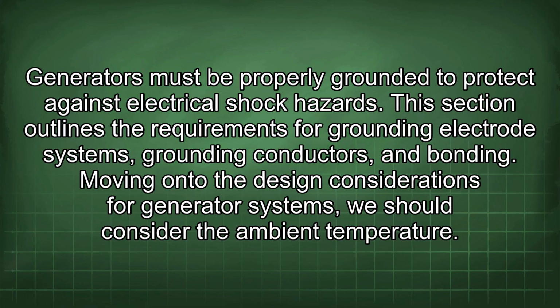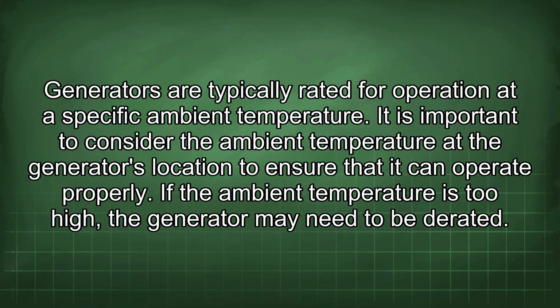Moving on to the design considerations for generator systems, we should consider the ambient temperature. Generators are typically rated for operation at a specific ambient temperature. It is important to consider the ambient temperature at the generator's location to ensure that it can operate properly. If the ambient temperature is too high, the generator may need to be derated.